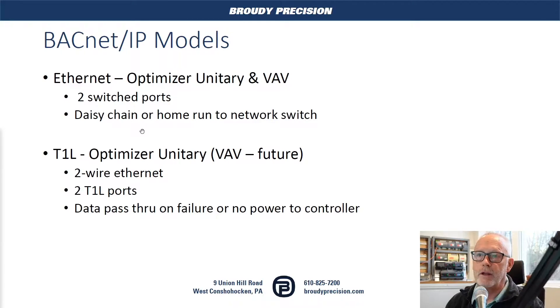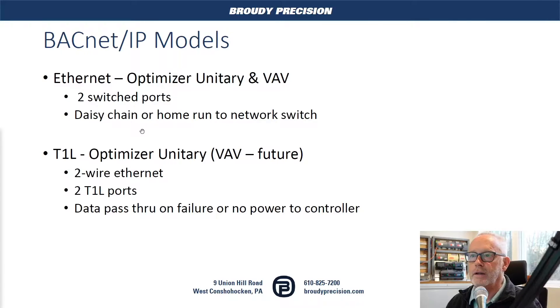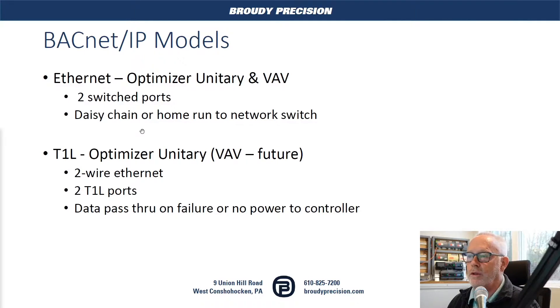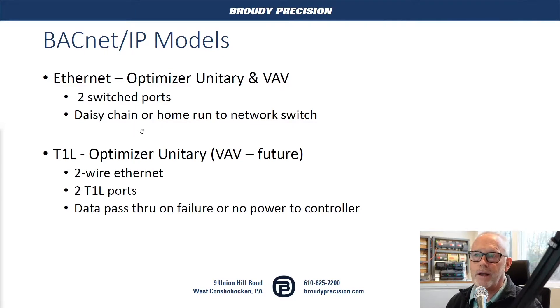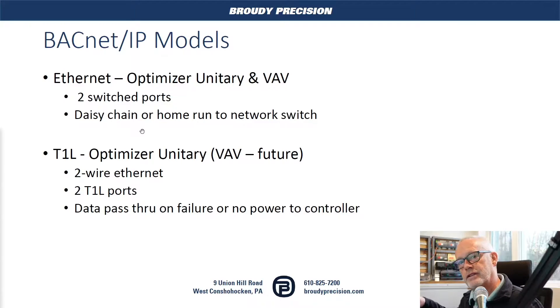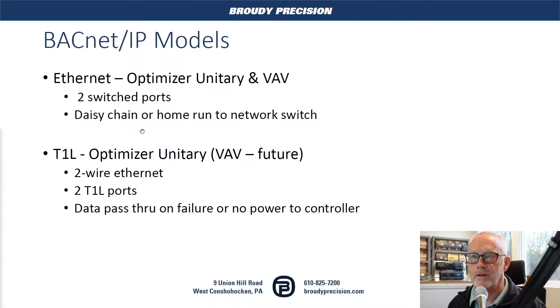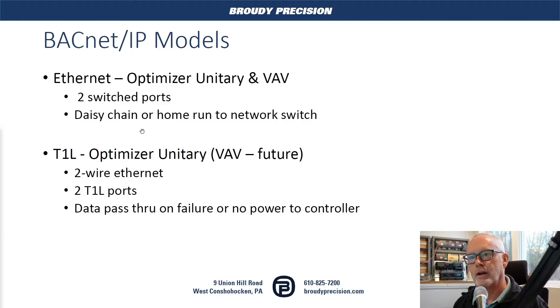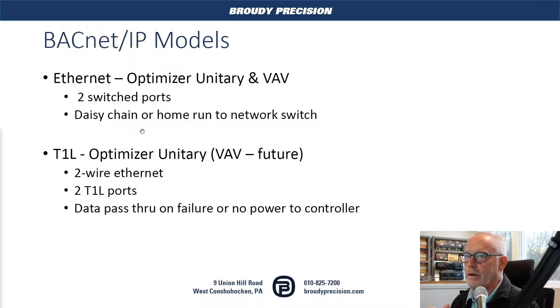In the Ethernet models with the switched port, if you lose power to any one of those controllers, you lose communications to anything downstream because you have no way to pass the data across those two ports. So that's one of the other big differences.